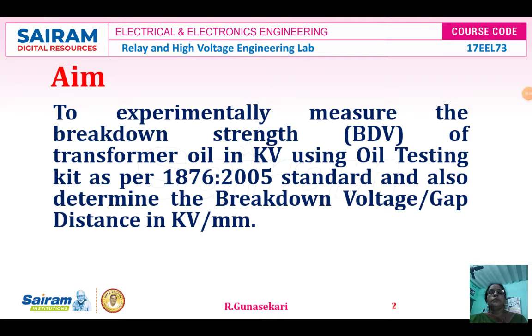Aim: to experimentally measure the breakdown strength or dielectric strength or breakdown voltage of transformer oil in kV using oil testing kit as per 1876-2005 standard, and also determine the breakdown voltage per gap distance in kV per millimeter. What is meant by 1876-2005 standard? This standard explains the measurement of high voltage.